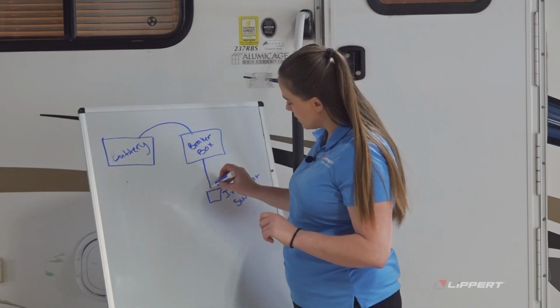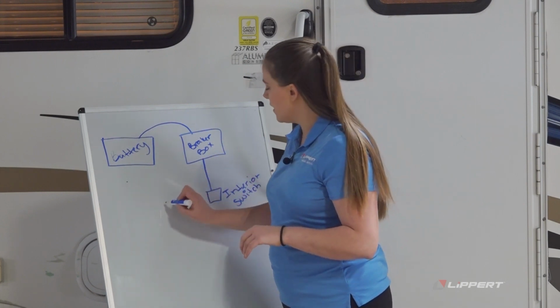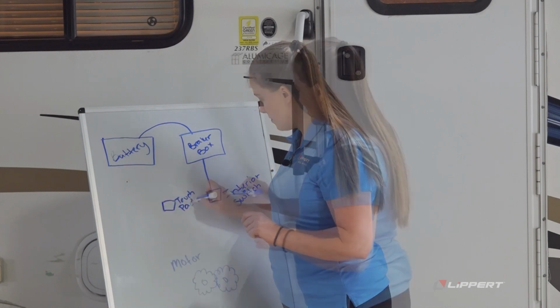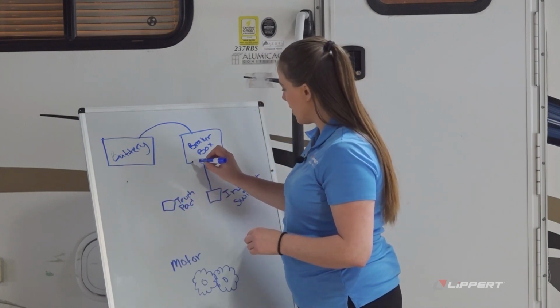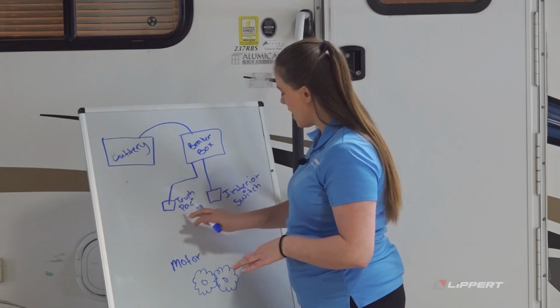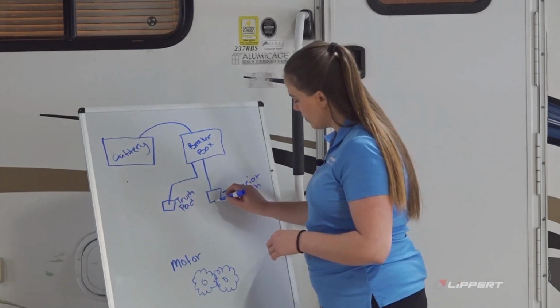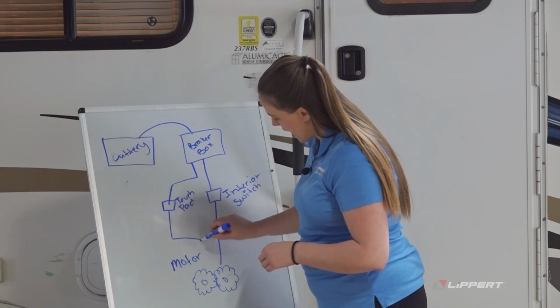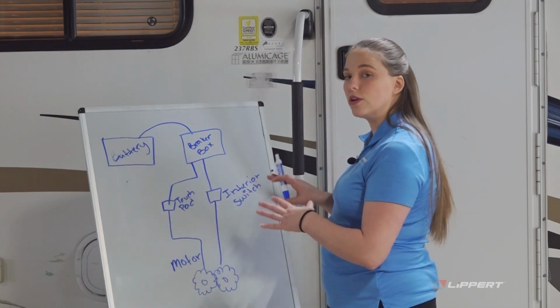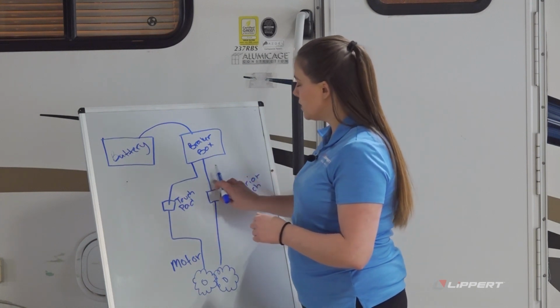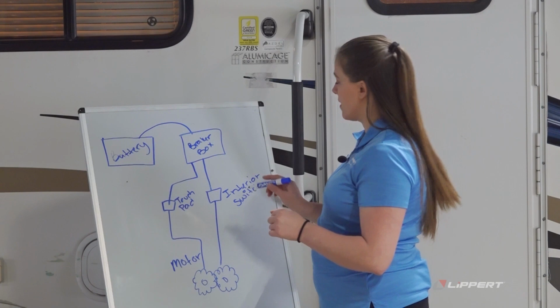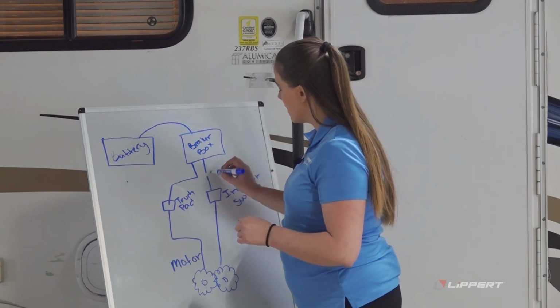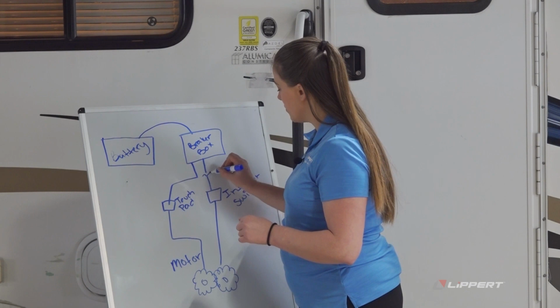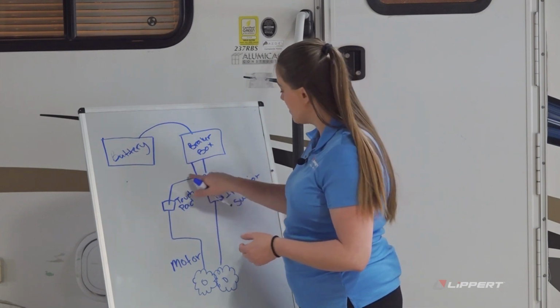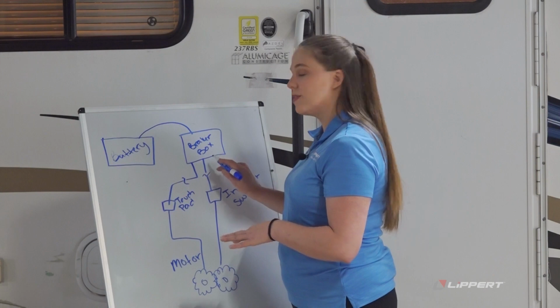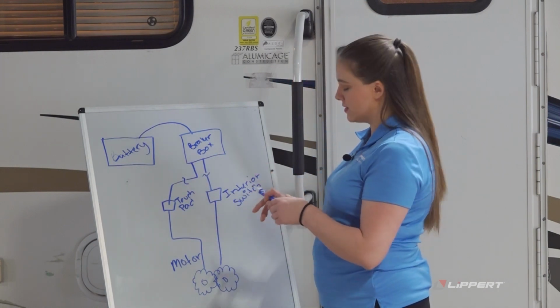You will have one power supply going to that switch, and then you will have your touchpad. So we have power going from our breaker box, our distribution panel, to our touchpad and to our interior switch, and both of those will supply power to our motor. And this will vary depending on your individual camper, but each of these will be individual power supply lines. And they will both need an inline fuse that will often be represented with a squiggle on wiring diagrams. And both of these fuses should be 15 amp fuses.